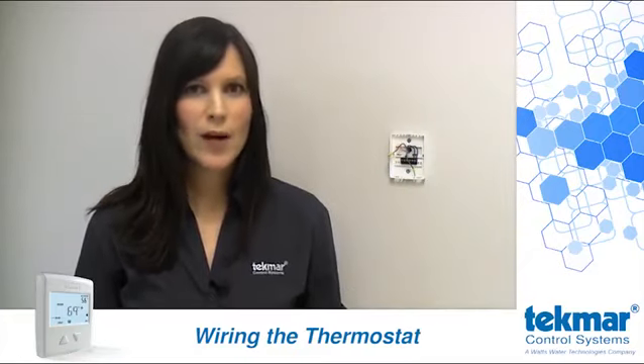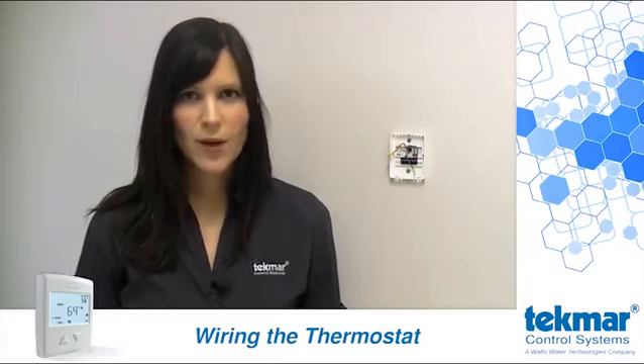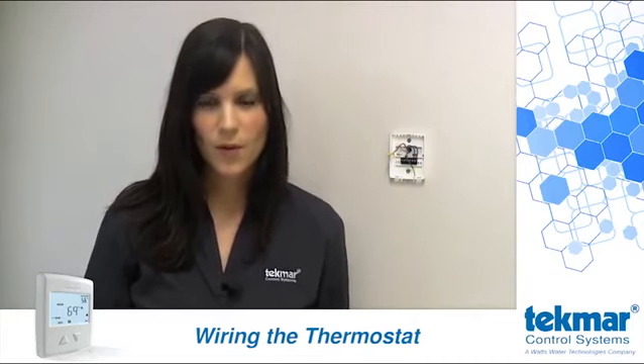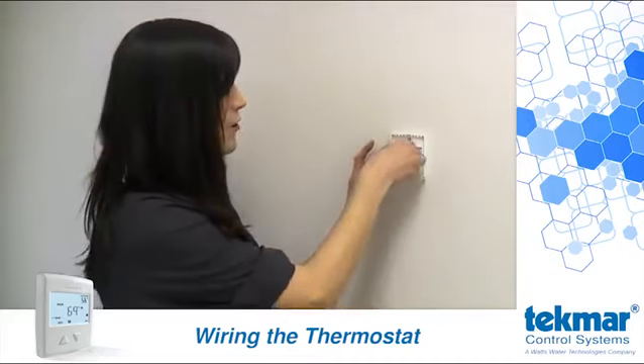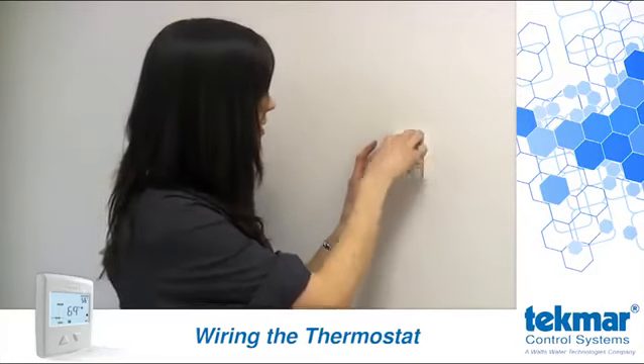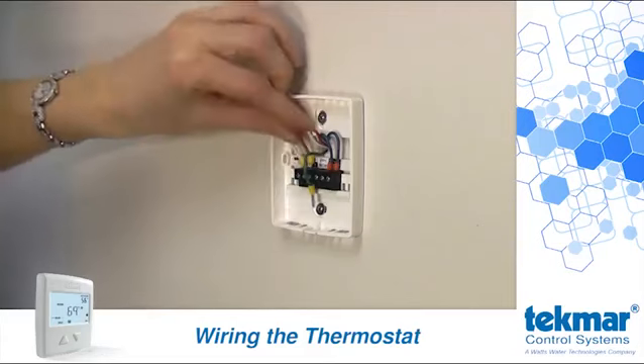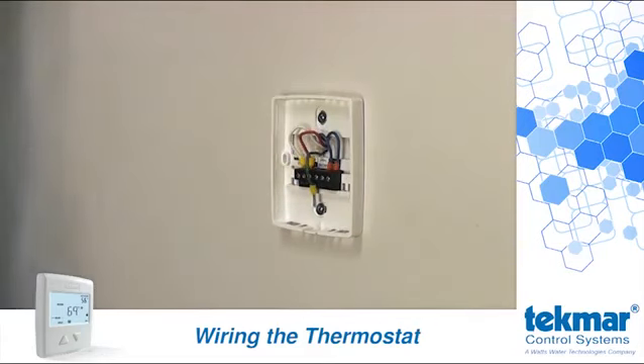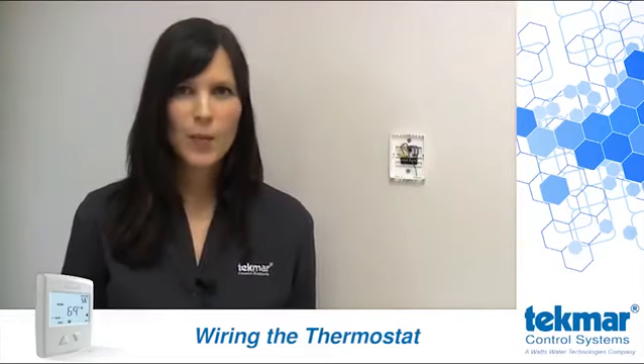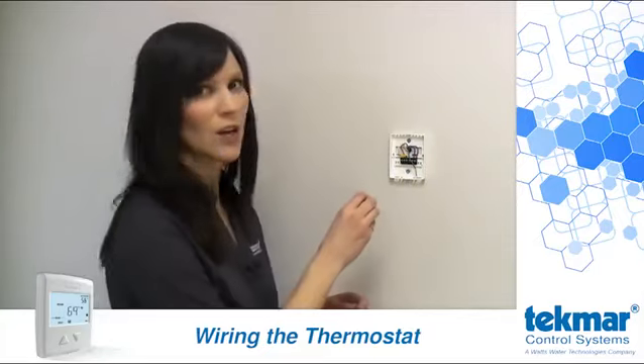I'm going to demonstrate wiring the thermostat to a zone valve with power from a 24-volt transformer. We'll connect the R from the transformer to the R on the thermostat. Likewise, we'll connect the C from the transformer to the C on the thermostat. We'll add power to the heat relay by installing a jumper between R and RH.